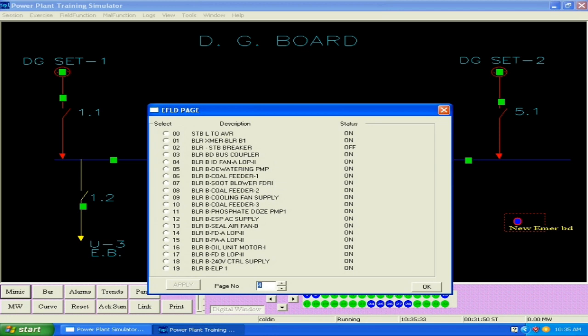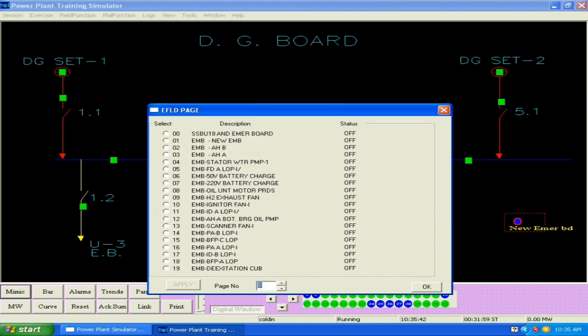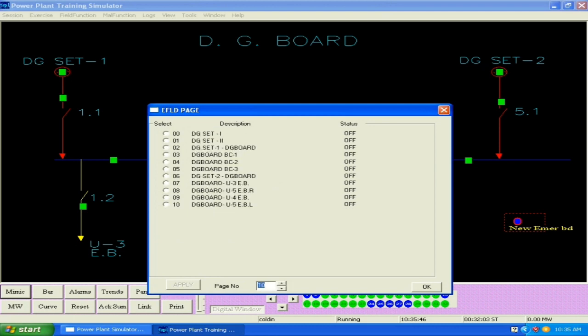On page number 4, electric field page number 4, you have to put on the supplies from DG set 1, incomer means going to DG set 1, then DG set 2, 02, then index number 03 is DG board, going to DG board, index number 3, 4, 5 you have to make them on, and then index number 7 is the DG board to unit 3 emergency board. So there are 2 units, 3 and 4, so one of them would be 3 number. So the supply for unit number 3 emergency board from DG board will be going from index number 7. That also you have to make it on.